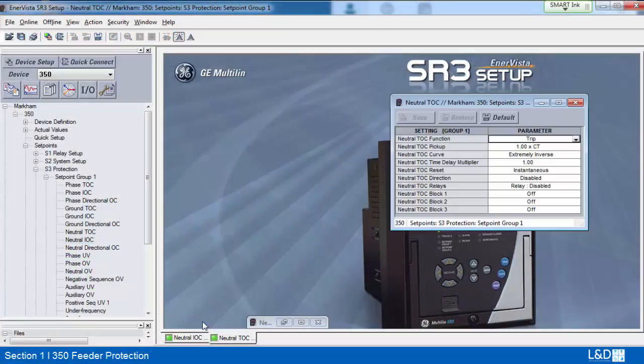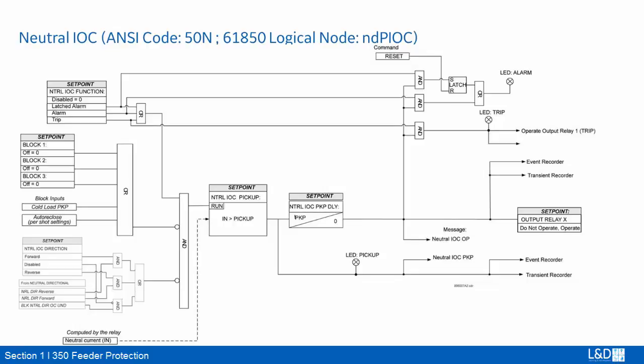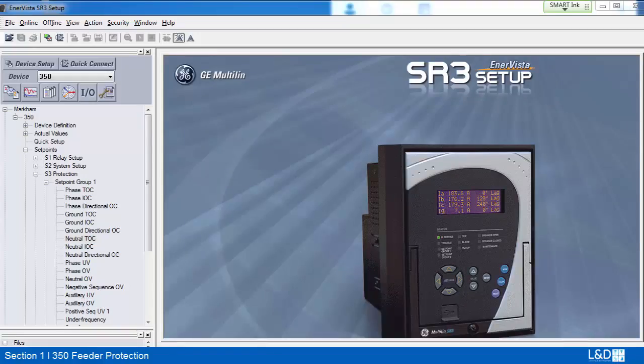Neutral IOC and neutral TOC have exactly the same settings as phase IOC and TOC. The difference is that the input is the calculated neutral current instead of the measured phase current. From the logic diagram of neutral IOC, we can see the IN input is computed by the relay. The function can be blocked by three digital inputs: cold load pickup, auto reclose, and directional.